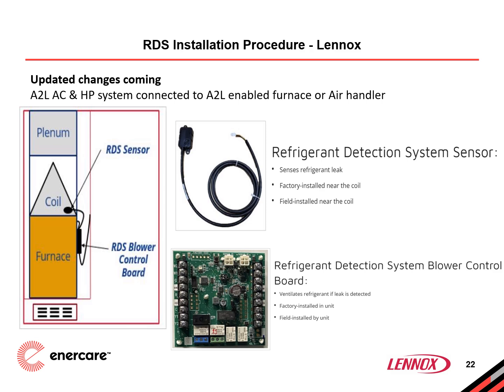the Lennox RDS system is a factory or field installed safety, designed to support the safe operation of A2L refrigerant systems, specifically within their air handlers, coils, and furnaces. New A2L rated product is already being shipped by Lennox. However, there are retrofit RDS kits for products that are not currently equipped.